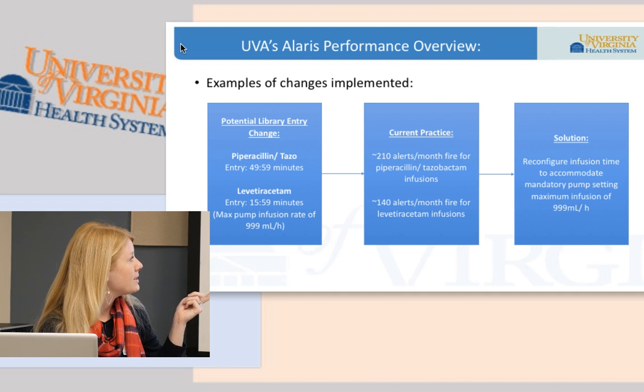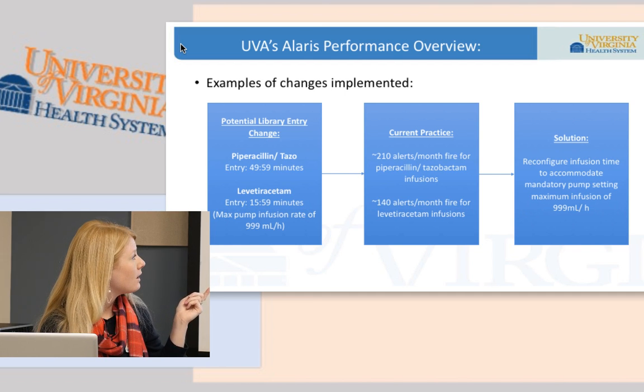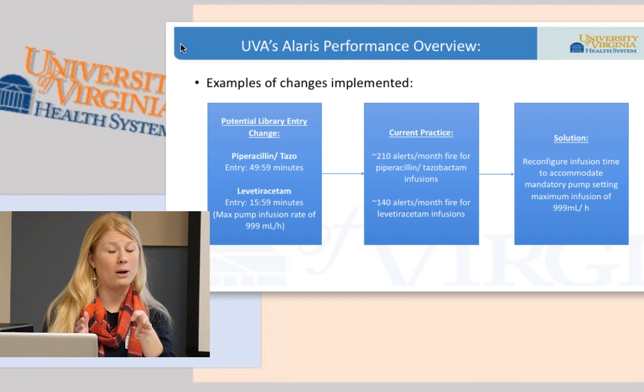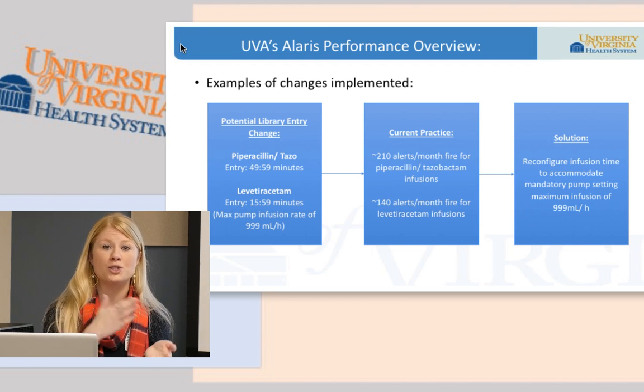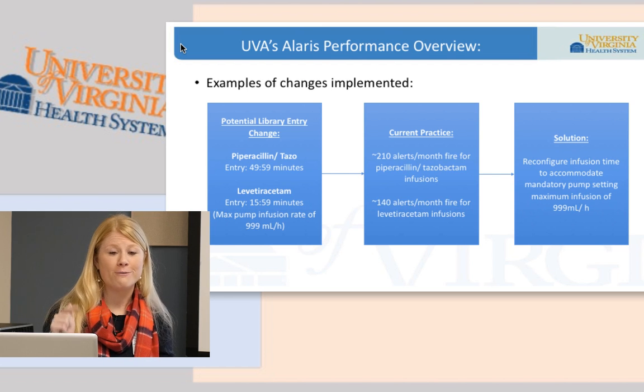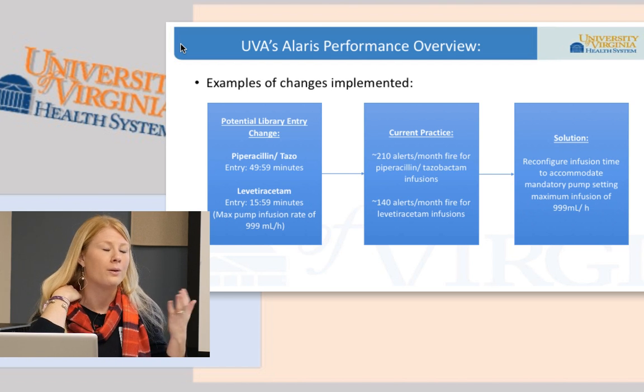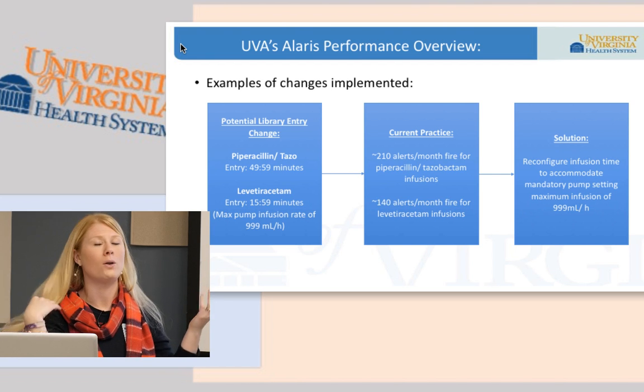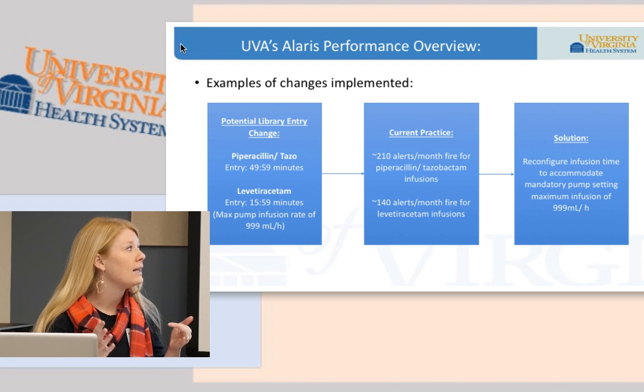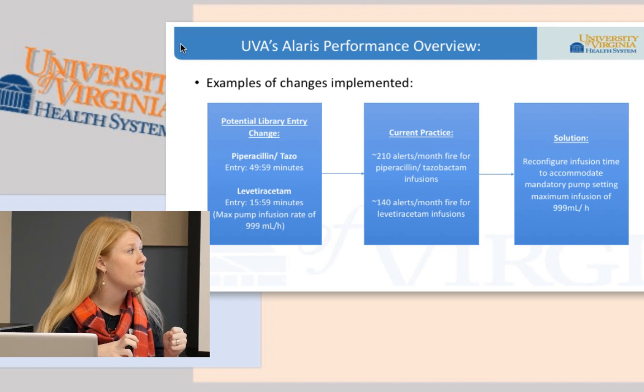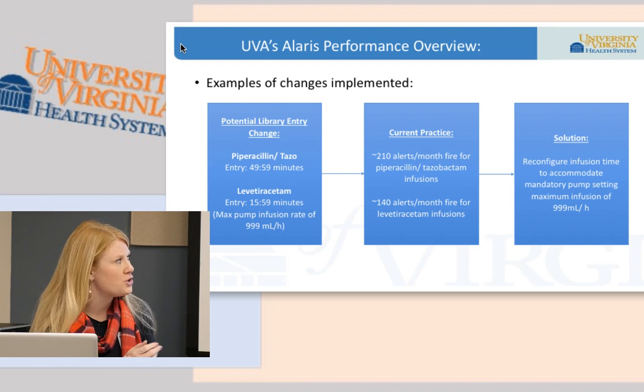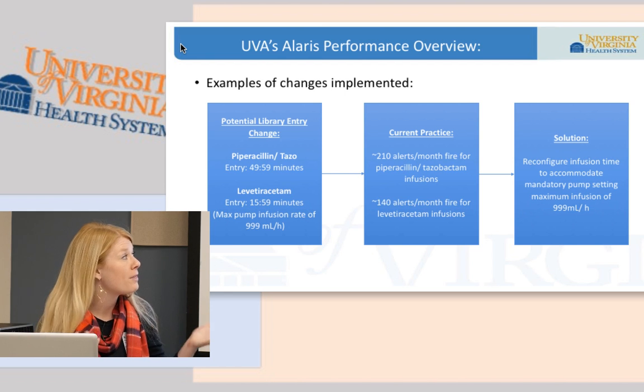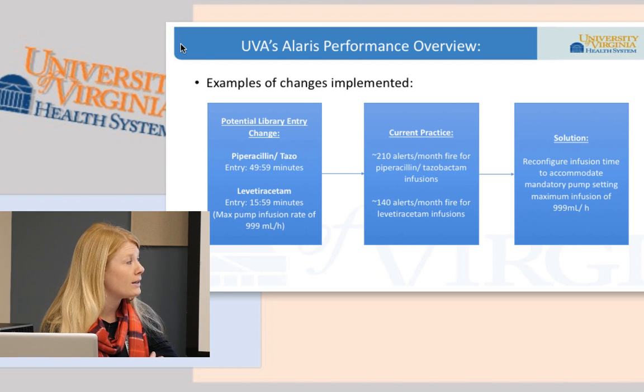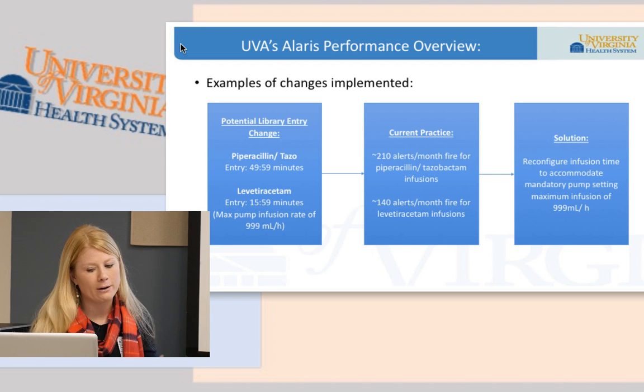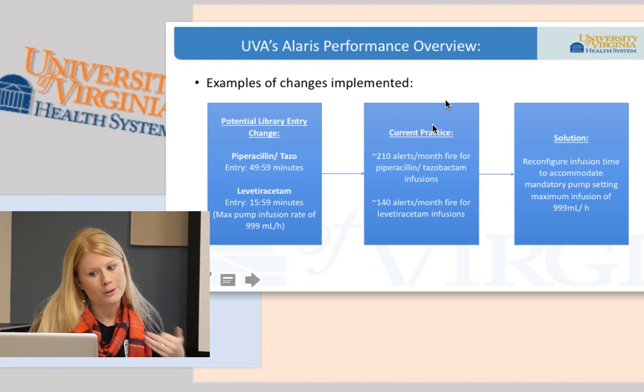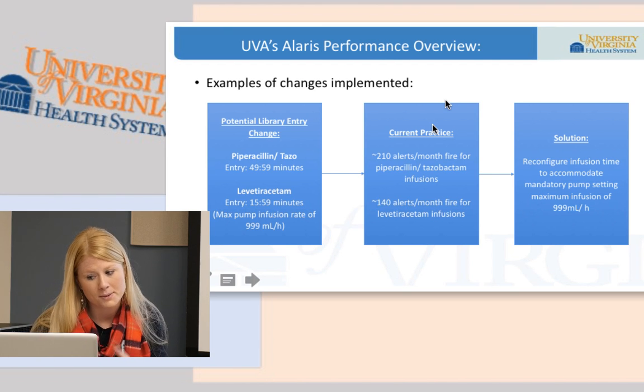For the levetiracetam, the order was calling for a 250 mL bag to be run in 15 minutes, while the max is 249.5 milliliters per 15 minutes. So the pump was programming an error, even though it really wasn't an error. We have since increased the default infusion time to 16 minutes, which allows the 250 mLs. But without the CQI data, we didn't know that these alerts were firing. So we're hoping to reduce some of that alert fatigue with some of these easier fixes.